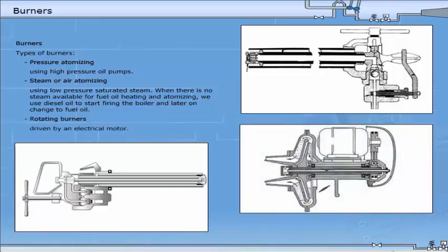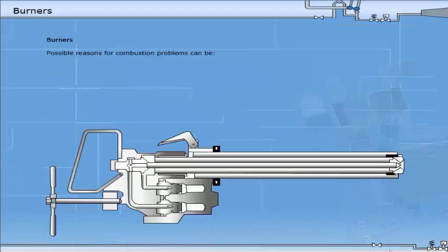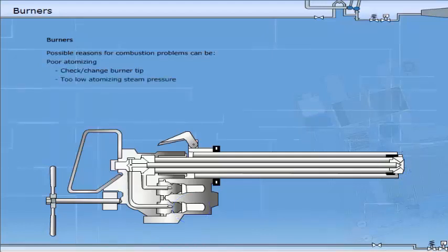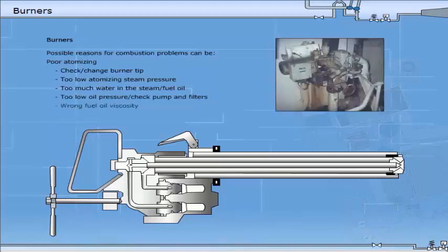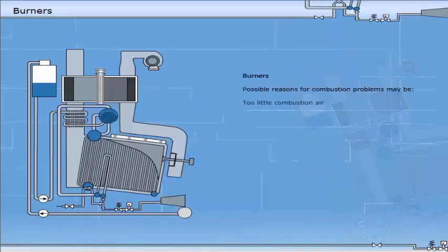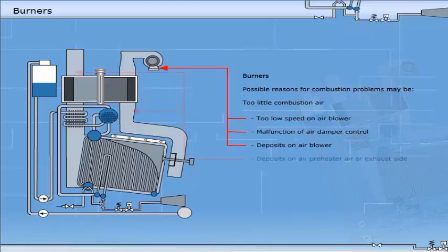Rotating burners driven by an electrical motor. Possible reasons for combustion problems can be poor atomising, check or change burner tip, too low atomising steam pressure, too much water in the steam fuel oil, too low oil pressure, check pump and filters, wrong fuel oil viscosity, too little combustion air, too low speed on air blower, malfunction of air damper control, deposits on air blower, deposits in the air preheater air or exhaust side, tuning of air-oil ratio controller, or deposits on economiser.